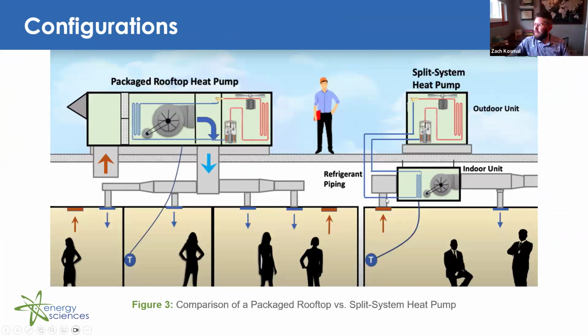Essentially, sorry, I don't know if you can see my pointer, but the split system on the right-hand side, that unit just below the roof level, would be your air handling unit, in which you would connect your refrigerant piping to that coil. The heat pump may come with its own coil, it likely would, but that would be installed at the air handling unit. So that's how a heat pump would be integrated into forced air cooling.